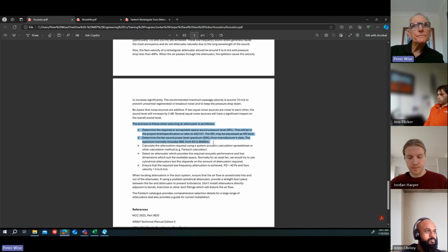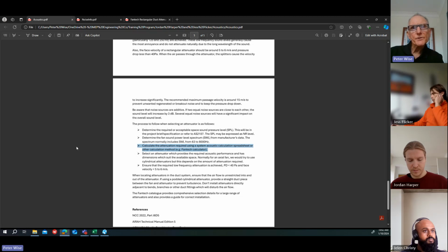Then the next thing is to go into the fan selection data and determine the fan sound power level spectrum, which is called the SWL, from manufacturer's data, and that's usually expressed from 63 through to 8,000 hertz. Then we need to calculate the attenuation required using a system acoustic calculation spreadsheet or some other method. And we looked at the FanTech method last week, which is probably the best one to use at this point in time. Going through that spreadsheet, it will tell you what attenuation you need to achieve the specified sound pressure level of the space, given the sound source, sound power levels, the ductwork, the fittings, internal insulation, and so on, once you've taken all that into account.